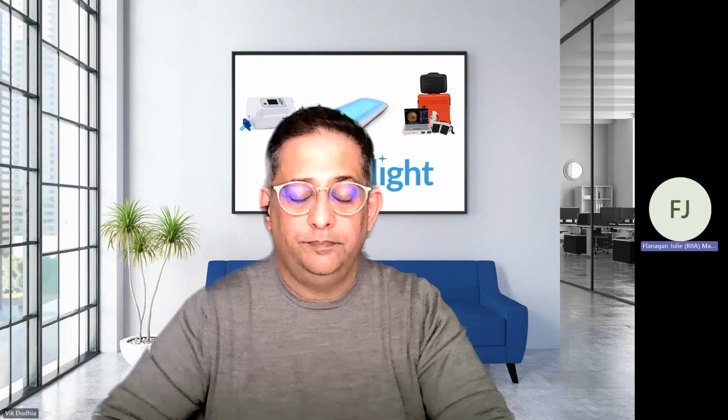So you would use the gain, but if you go too high on the gain, the images can become very grainy. So we tend to go up to a level of about 20 on the gain, maybe not much more than that. But you do a test. You're testing all the time while you're doing the images, and the intensity I would only go up to maybe 10 on the dark babies, and go up on your gain a little bit.